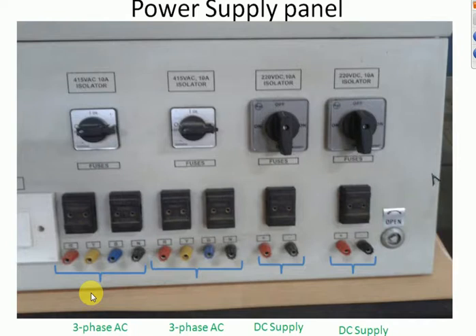Most importantly, you don't need a separate DC power supply derived from batteries or a rectifier. Instead, this DC power supply is derived right away from a reduced 3-phase AC, such that you get 220 volts DC. Most of the 3-phase ACs are the standard 415 volts, 3-phase, 50 Hz supplies.